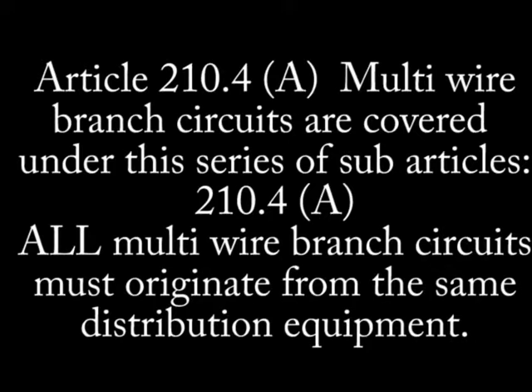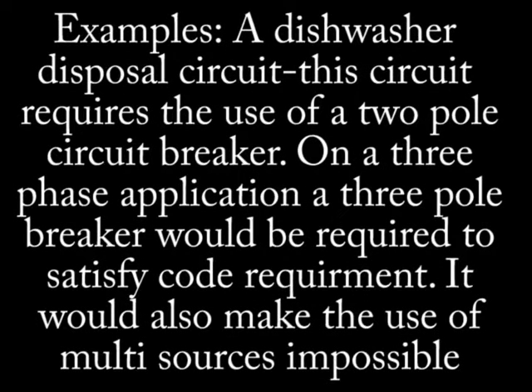Article 210.4 paragraph A. Multi-wire branch circuits are acceptable under this article. All multi-wire branch circuits must originate from the same distribution equipment. An example of this would be a dishwasher disposal circuit. This circuit not only requires that both legs originate from the same panel, but the two circuits are powered by a two-pole breaker.